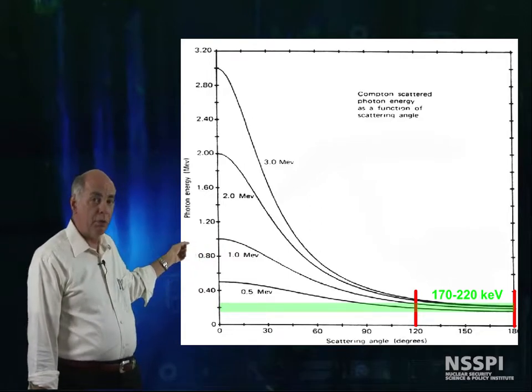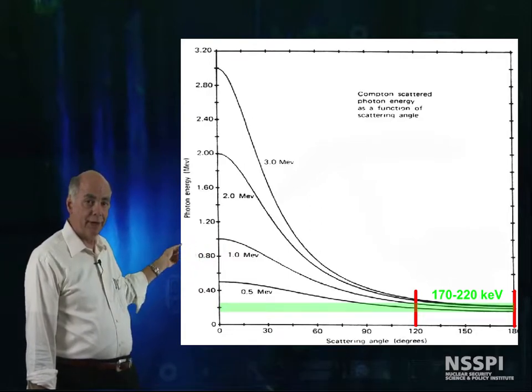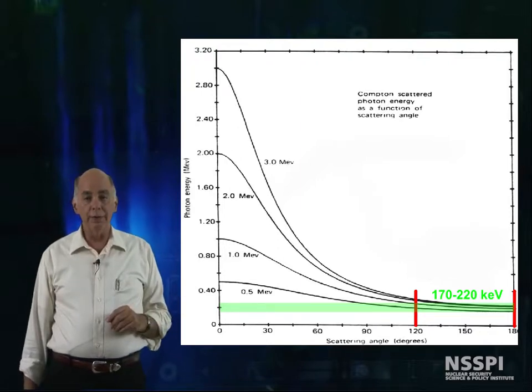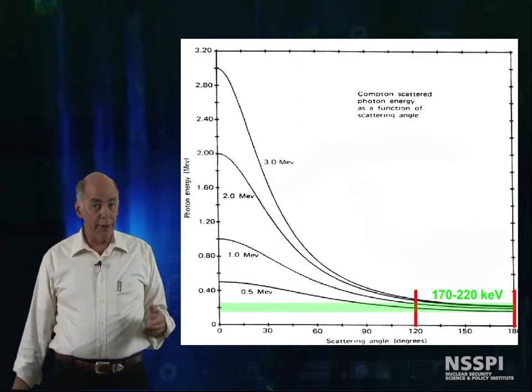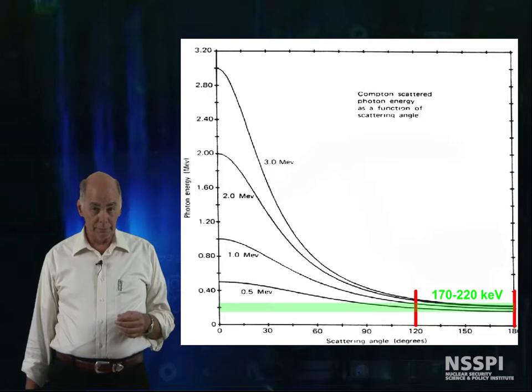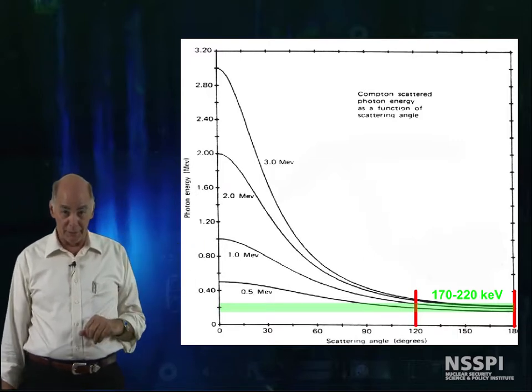This is important for Uranium-235 counting, because the principal identification energy is 186 keV. I'll show you an example of backscatter peak in a moment.